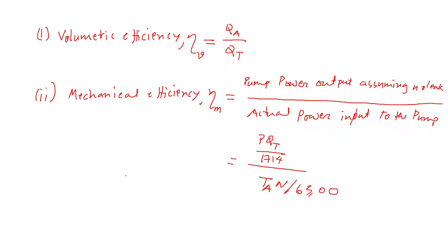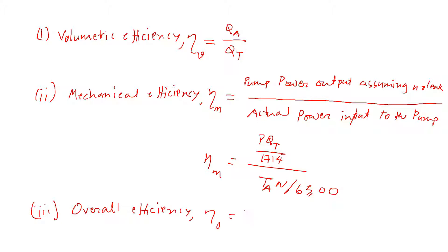That gives the mechanical efficiency equation. Now the overall efficiency is not really a third category but rather a combination of volumetric and mechanical efficiency. The overall pump efficiency, eta-O, is basically volumetric efficiency multiplied by mechanical efficiency.